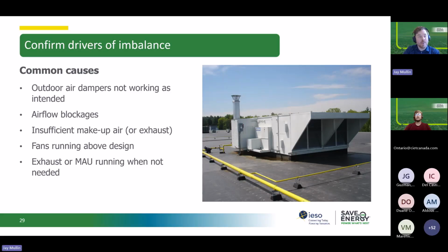Fans might be running above design. If a VFD is malfunctioning or no longer connected or operating properly, that fan might be running full speed when it shouldn't be or wasn't previously. Another common cause is exhaust or makeup units running when they're not needed. So if there isn't the need for the exhaust, but you still have a lot of exhaust fans running, that can cause challenges as well. So these are all common issues with that.